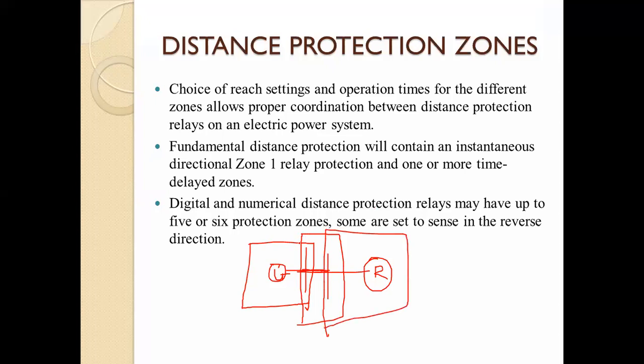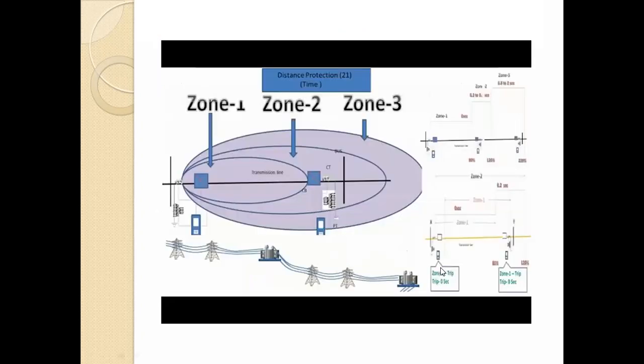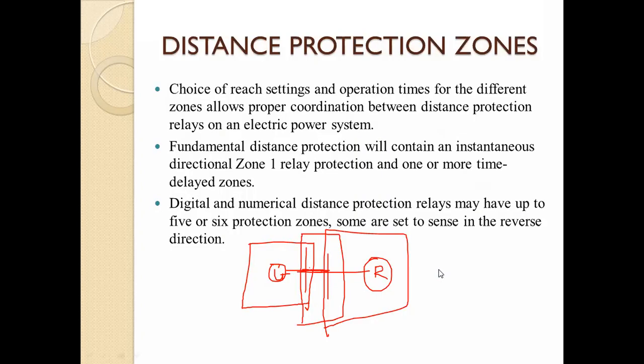Okay, that is called overlapping of zones. Means what? If any fault occurs anywhere at a time, two circuit breakers will trip. Okay, nearest will trip first, but more than one circuit breaker can trip there. Also, the advantage is that no point from the generating to the receiving station will remain without a protective zone. Okay, now here the distance protection zones are different, means we are using the primary protection and the secondary, meaning backup, protection.